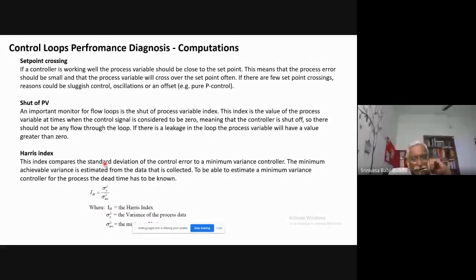Okay. So what we do here is we calculate from the process data this standard deviation of the process signal, and also the standard deviation that is coming from the minimum variance controller. For calculating this, we need to have an idea about the delay time that is present in the control loop. So if you know about the delay time, then it is possible from the data that is available to calculate this standard deviation from the minimum variance control. Here again, for calculating this minimum variance controller standard deviation, we fit the time series model to the process data, then estimate this variance from that. Okay.